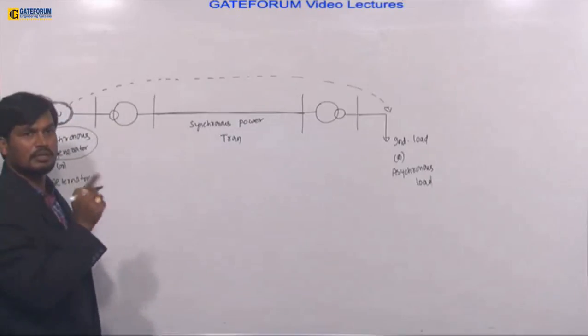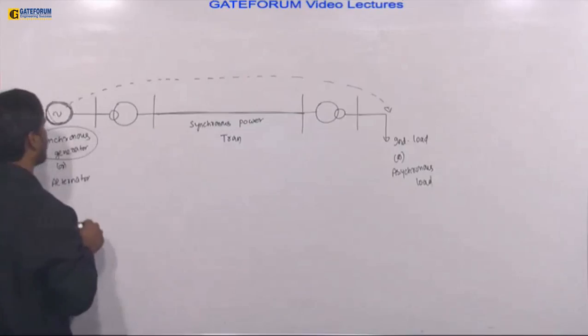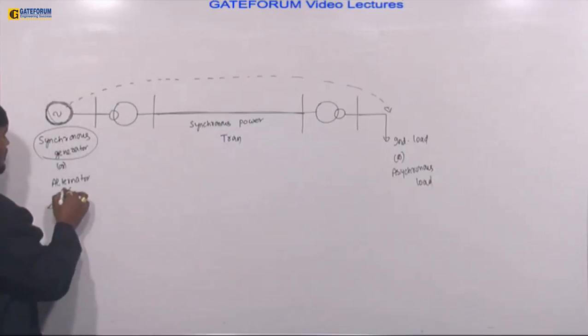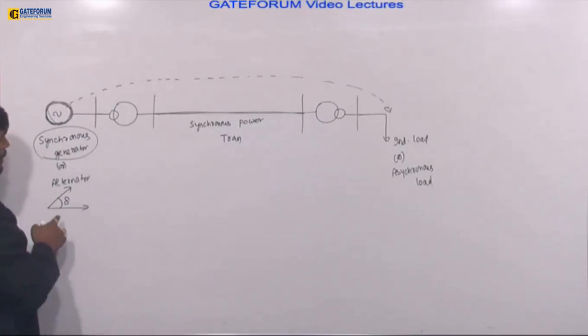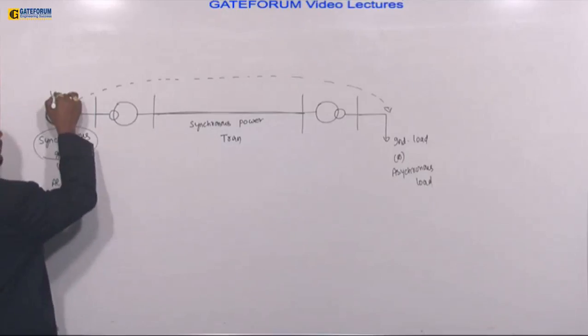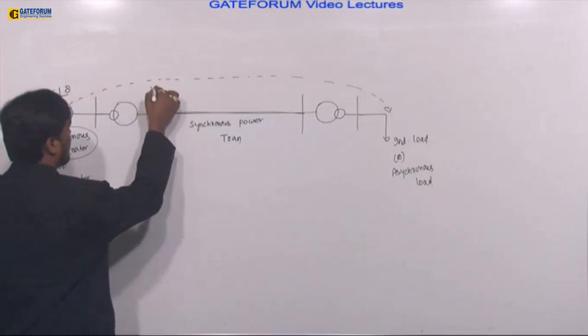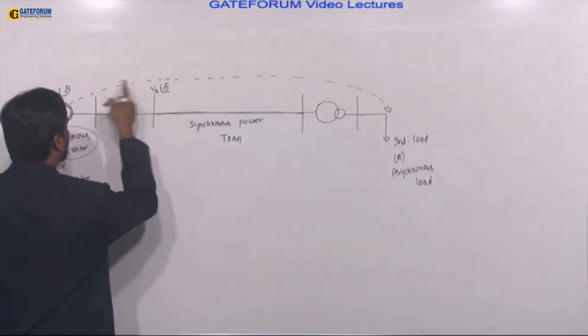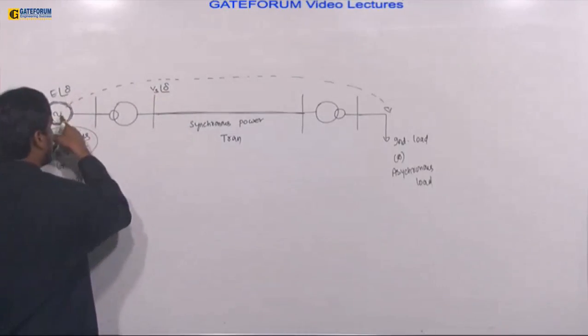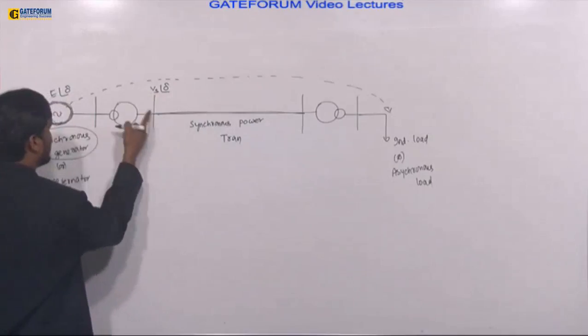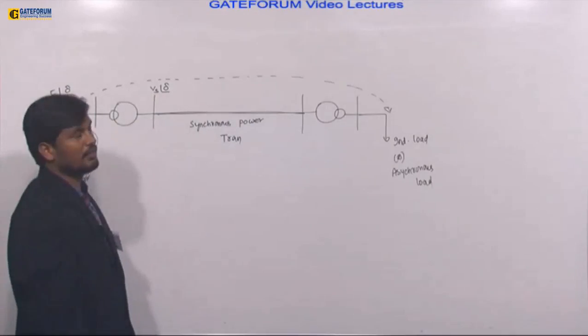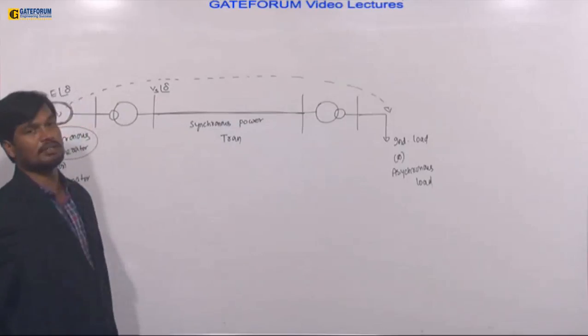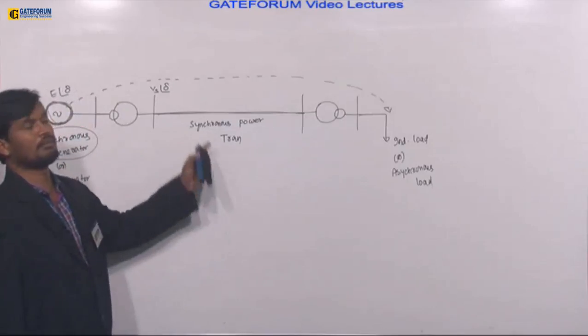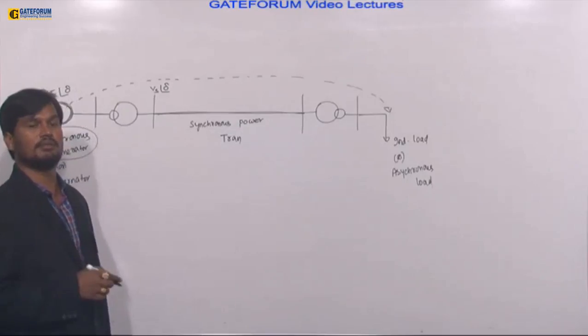What is the meaning of synchronism? Both are working at the same speed. How to tell both are working at the same speed? The angle between stator and rotor flux of the alternator is delta. When this angle is constant, the stator speed and rotor speed are also in synchronism. The angle at the alternator is delta, and the sending end voltage Vs is at angle delta. When the angle at the alternator is same as the angle at the sending end, it means both are working under synchronism, and the alternator is delivering maximum real power to the load point through the transmission lines. Therefore the system is more stable.